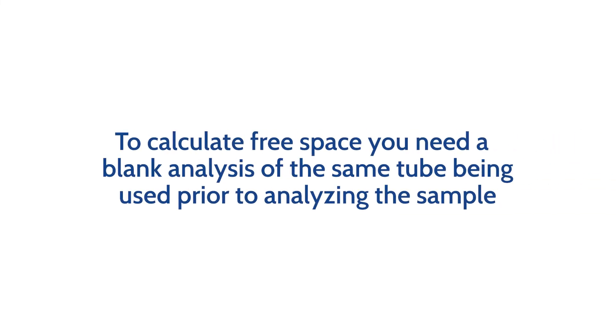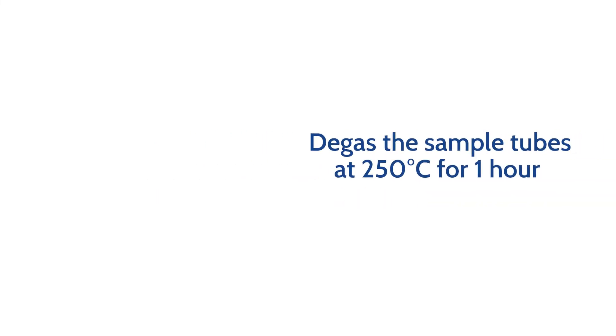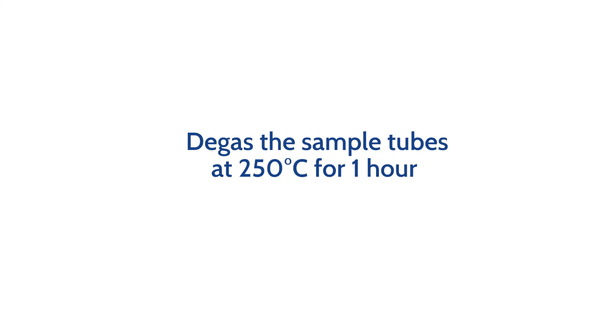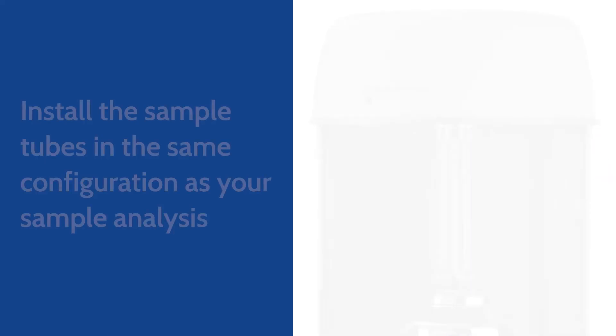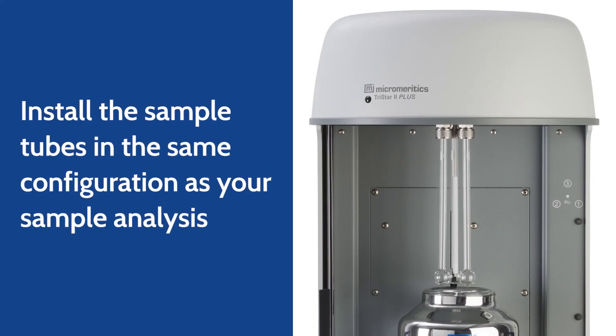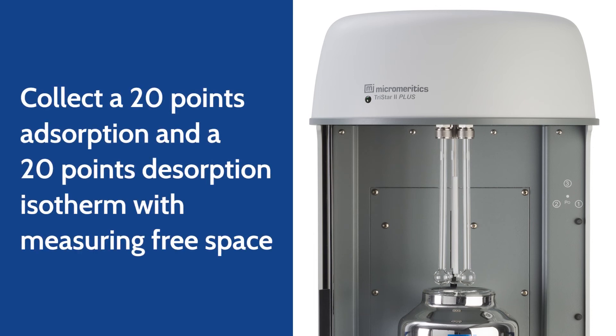To calculate free space, you need a blank analysis of the same tube being used for the analysis completed prior to analyzing the sample. For a blank analysis, degas the sample tubes that will be used in the sample analysis at 250 degrees Celsius for one hour. Install the blank tubes on the sample port with the same sample tube configuration as a sample analysis and collect a 20 points adsorption and a 20 points desorption isotherm with measuring free space.